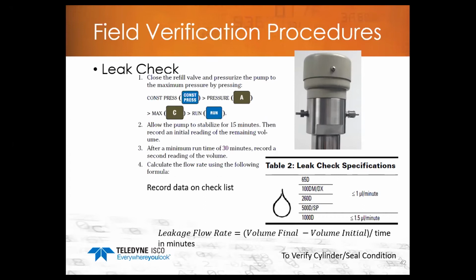Then after that time frame, whether it be an hour or 2 hours, you'll record an ending volume. Then with your starting and ending volume, you'll subtract your ending volume from your starting volume, and that difference divided by the number of minutes that you've been running the leak check will give you the leak rate of the pump.